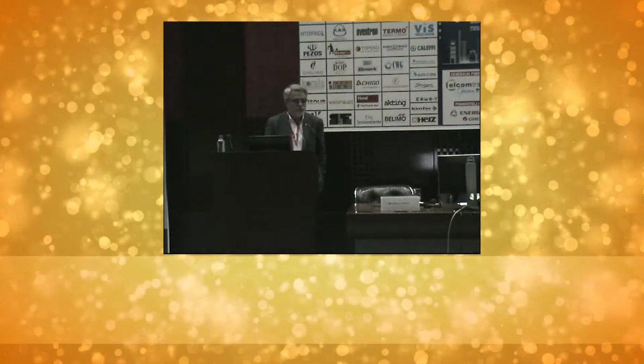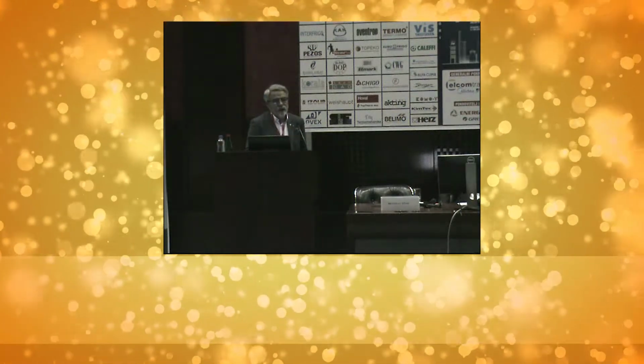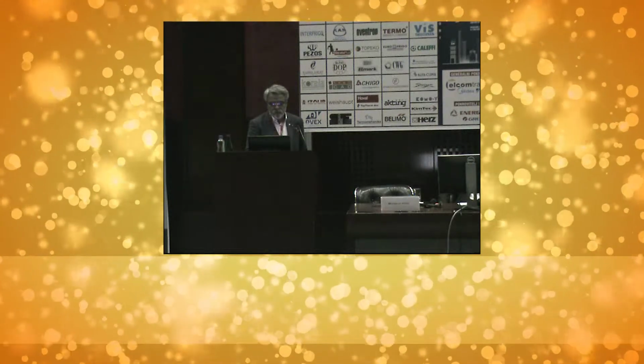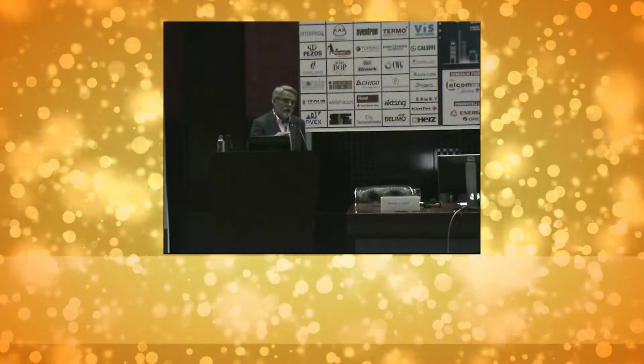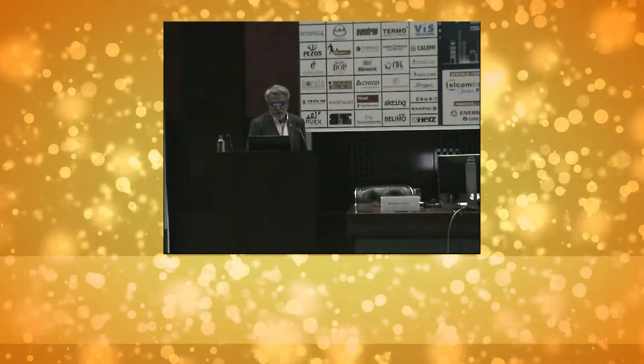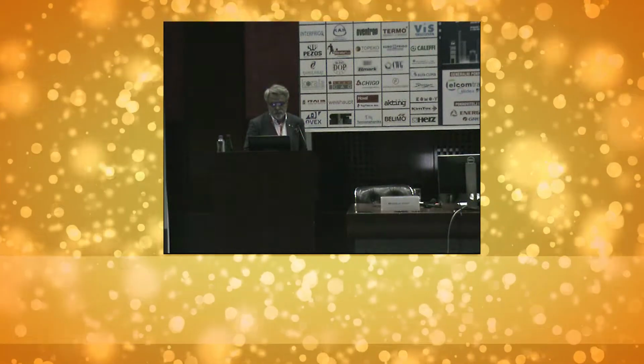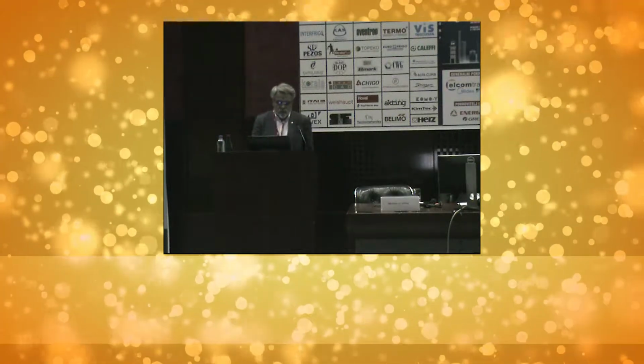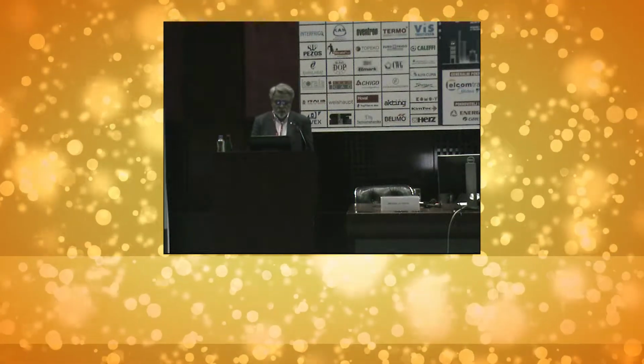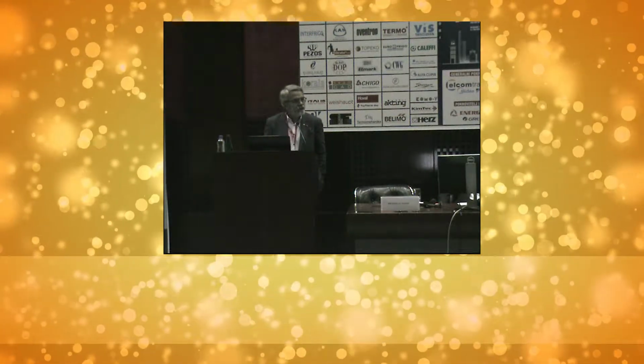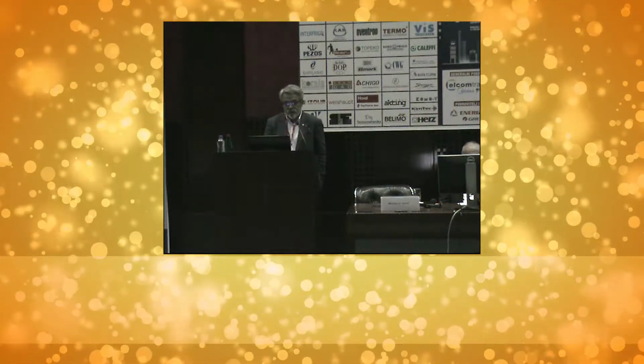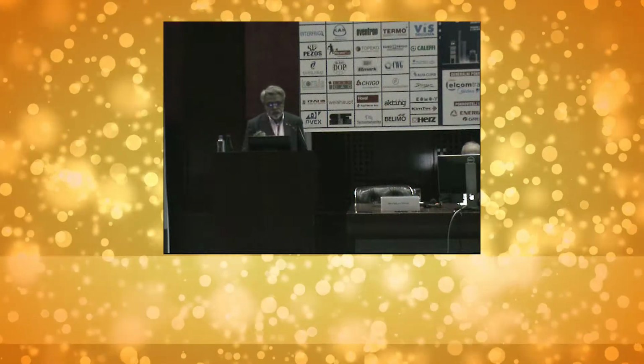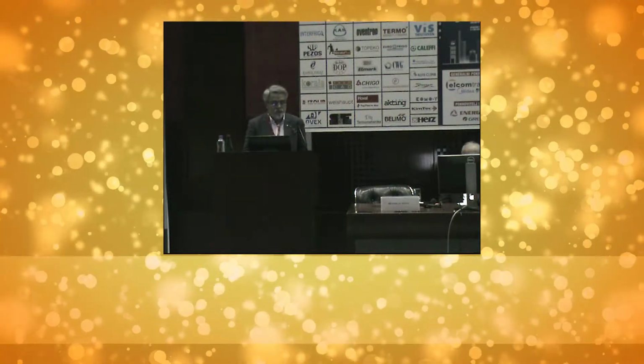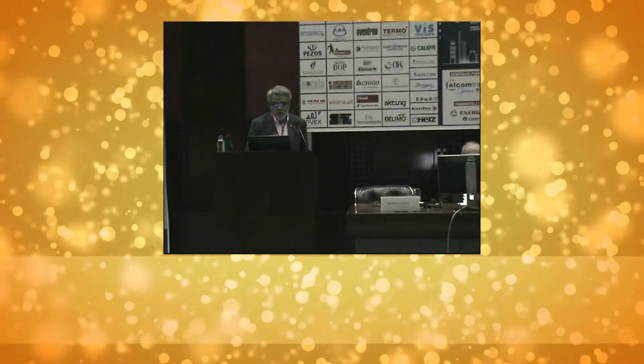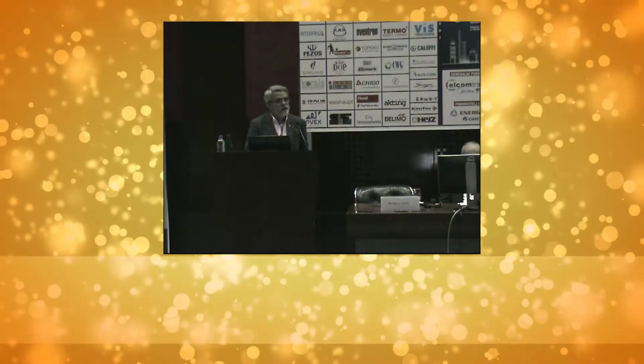Also, the cooling load necessary for making the ice is a little bit bigger. For cooling the slab and starting to make the ice, usually for such a surface of 1,800 square meters, we need for an indoor ice rink 450 to 500 kilowatts. And for making the ice, we need a cooling load around 300 to 350 kilowatts. And for maintaining the ice, we need 100 to 150 kilowatts.